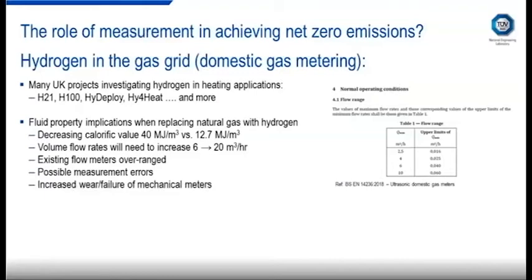And the reason for this is that hydrogen has quite different fluid properties compared to natural gas, and that has an implication for the flow measurement. So one of the biggest differences is a decrease in calorific value. It's about 3 times less for hydrogen than it is for natural gas. This means that to achieve the same energy density, you'll likely have to increase the flow rates. So a flow meter currently working at 6 meters cubed per hour would probably have to operate at around 20 meters cubed per hour if it was using pure hydrogen.